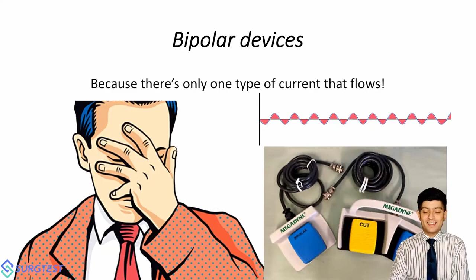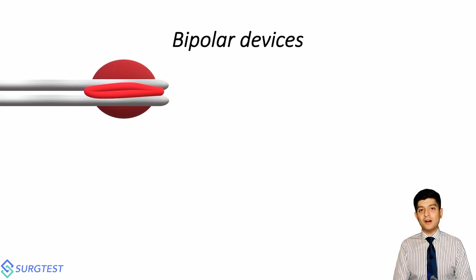So in my OR, I don't shout cut and coag. If I'm training someone, I just say yellow pedal or blue pedal, or continuous or intermittent duty cycles, because that's essentially what they are, right? It's not that the coagulating current can't cut and the cutting current can't coagulate. So we need to get over this in our minds and truly understand the fundamental principles of these energy devices to be able to use them with some amount of confidence in the OR. So again, with bipolar devices, you'll end up forming an extremely effective seal by using a low voltage continuous waveform current that you see on screen.